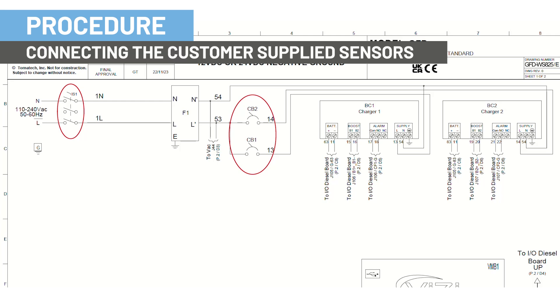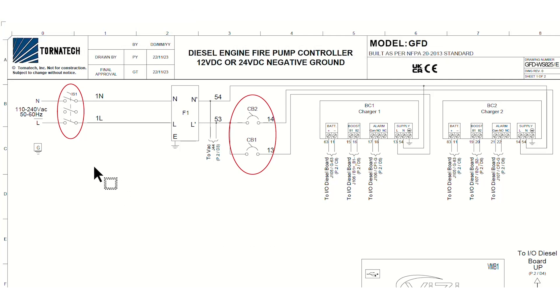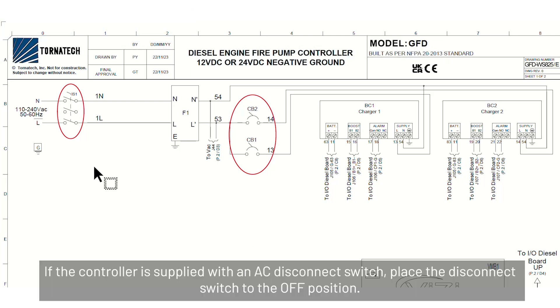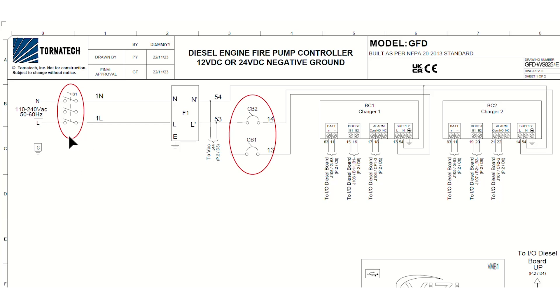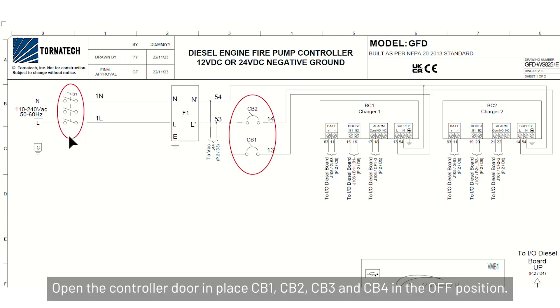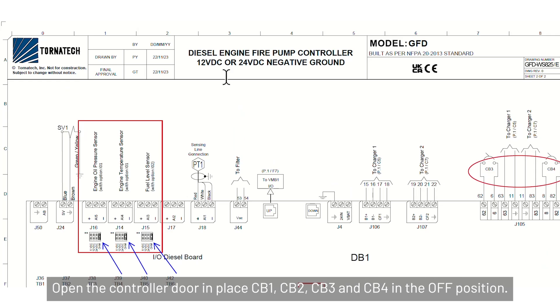Procedure: connecting the customer-supplied sensors. If the controller is supplied with an AC disconnect switch, place the disconnect switch to the off position. Open the controller door and place CB1, CB2, CB3, and CB4 in the off position.